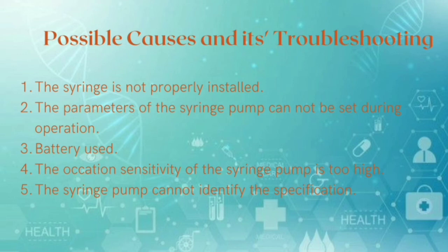Next point is battery used up. In this issue, the device cannot be turned on. For that, connect the syringe pump to AC power supply to charge the battery.